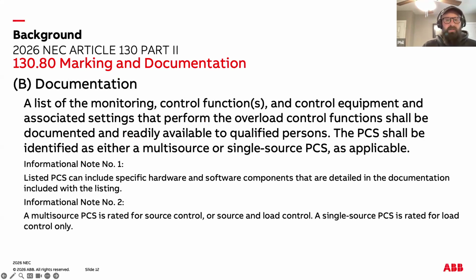130.80(B) continues the documentation requirement for how a PCS performs its overload control function. It ensures that anyone servicing or inspecting the system can clearly understand what is being monitored, what is being controlled, and how the PCS is configured. Beyond just labeling, a PCS must have a readily available document that lists the monitoring methods, control functions, and control equipment the PCS uses to prevent overloads. It also has to have the specific settings associated with those functions, whether the PCS is a single source or multi-source PCS. And the two informational notes clarify that a listed PCS includes defined hardware and software.